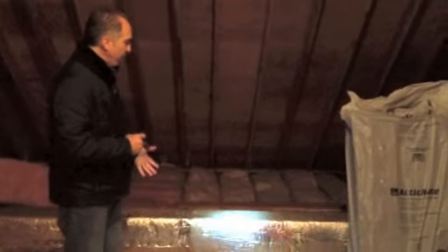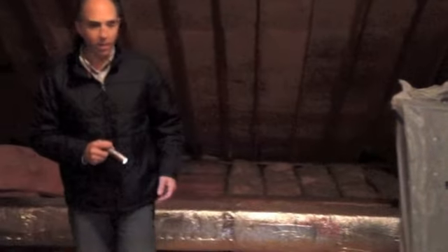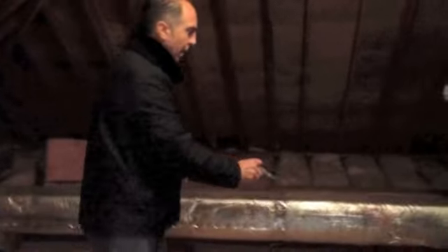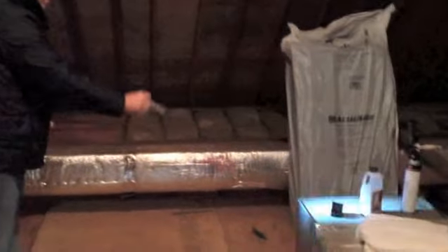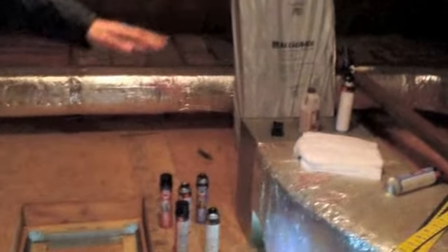This ductwork actually is heating and cooling. This is fairly well insulated, not superbly insulated, but better than bare metal. If all the ductwork was bare metal like this, then we actually would be air sealing all of that ductwork. We're still going to do some air sealing on this system, and if the ductwork is laying on the floor, we actually can insulate over that ductwork. So we see that a lot in older homes that have old ductwork in the attic. So not only can we improve the air seal of the house, improve the insulation in the attic, but we could dramatically improve the ductwork, which actually can be losing 20 to 30% of your heat through leaky ductwork in the attic.